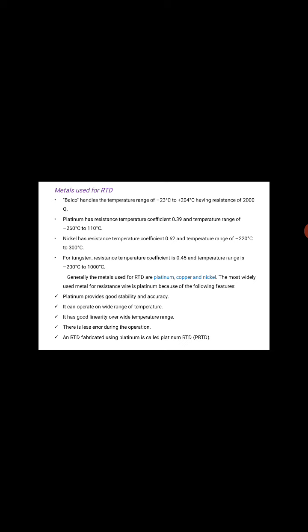Generally, the metals used for RTD are platinum, copper, and nickel. The most widely used metal for resistance wire is platinum because of its following features: it provides good stability and accuracy, it can operate over a wide range of temperature, it has good linearity over the wide temperature range, and there is less error during operation. RTD fabricated using platinum is called a Platinum RTD, that is PRTD.